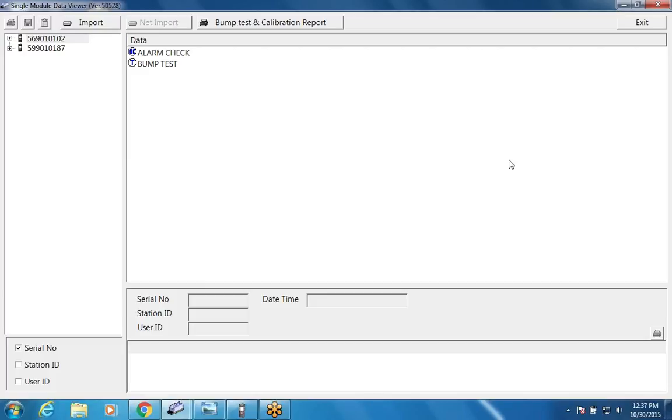And then if you look at the back of the unit, there are places at the top and kind of in the middle where you can link units together. So if you have 10 of them connected together, it comes with some little brackets that will hold everything nice and snugly together. Because when you push the 2 units together, you can see on this side there's a connector at the bottom and then your gas connections that will daisy chain to the next unit.